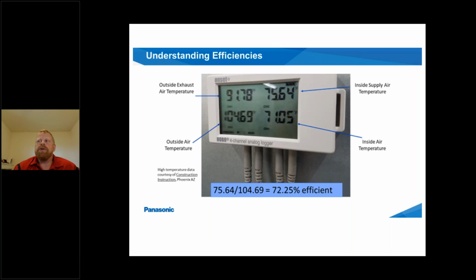Here's a quick slide that helps you understand the efficiencies of an ERV. By this slide, the outside air temperature on a typical summer day is 104 degrees. Your conditioned air inside the home is 71 degrees. Those two air streams will cross through the core of the ERV, and the air never touches to cross-contaminate, but the inside air will temper the outside air. So the air that gets forced through and dropped into the home goes from 104 degrees to 75 degrees. And if you run the numbers, that is a 72% efficient transfer of heat. So that 104 is now 75.